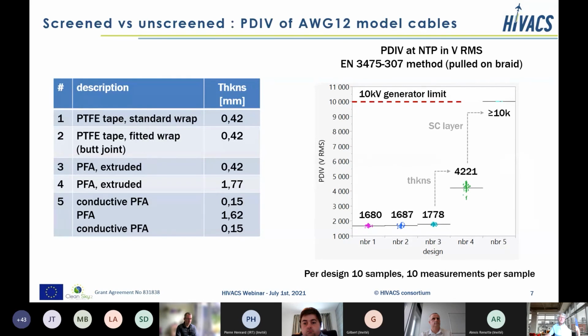In a first step, we tested different model cables using a conductor size of gauge 12. So we have been using 5 different designs. The first 2 use a PTFE tape wrap insulation, one with what we call a standard wrap and one with a fitted wrap. The fitted wrap is supposed to generate fewer voids at the overlap of the tape. And a third one uses extruded PFA insulation. All 3 have the same thickness of 0.4 millimeter. And then we have thicker extruded PFA insulation of 1.7 millimeter or 1.8 millimeter. And then the 5th one is a screen cable with semiconductive layers on the conductor and on the insulation.